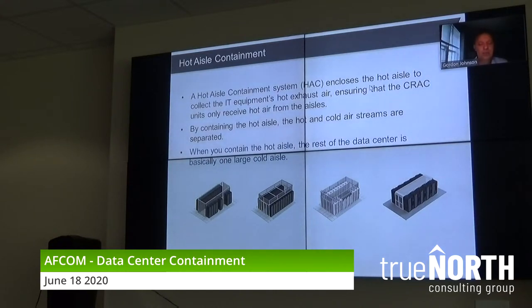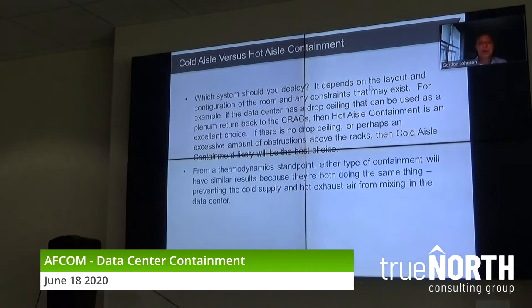Hot aisle containment works great with a data center. If you're thinking of doing in-row cooling, hot aisle containment's a great way to go. Cold aisle containment works just as well. So look at that first question in that bullet point. Which system should you deploy? It depends. So when we go into an existing data center, and the customer says, should I go hot or cold? 90% of the time, the choice is made for us just looking at the building themselves.